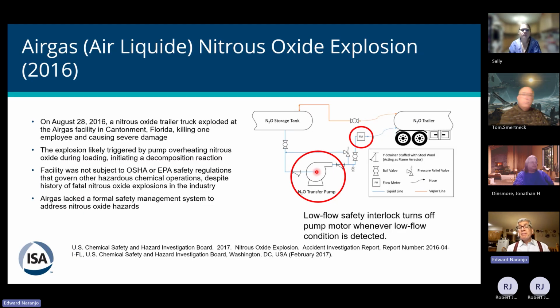And what has been typically done here is, it's a very crude mechanism, but the way in which a pump dry condition is identified is by having a flow meter. The flow meter measures the flow rate of the liquid. If that flow rate is within a certain minimum parameter, the pump is considered to be fully lubricated through the use of that liquid.